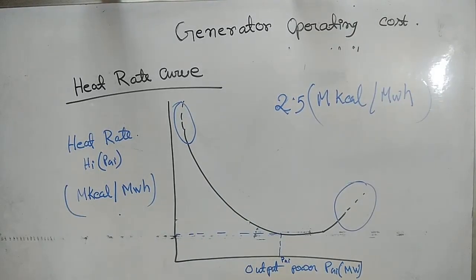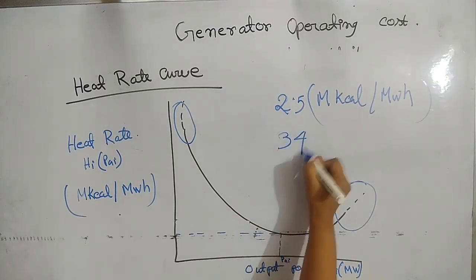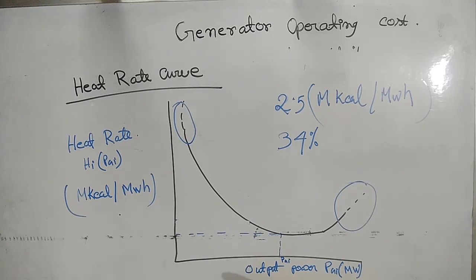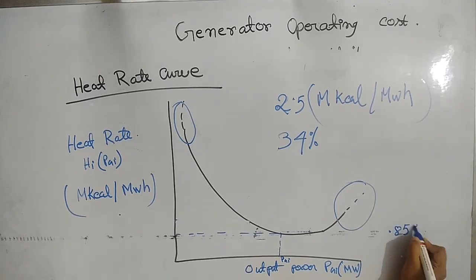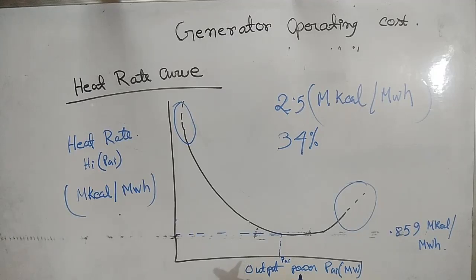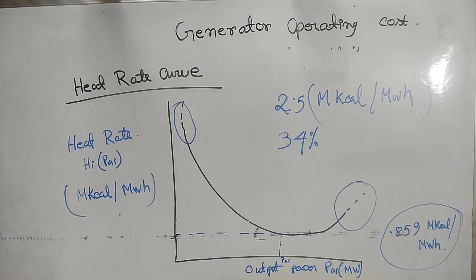This gives a peak efficiency of about 34 percent. Since all input energy is not converted to electrical energy output, the heat rate indicated in this figure can be further reduced at all points if the conversion from input fuel energy to electric energy is 100 percent. For 100 percent conversion, the heat rate is approximately 0.859 M kilocalorie per megawatt hour.